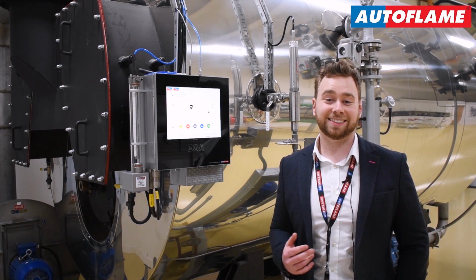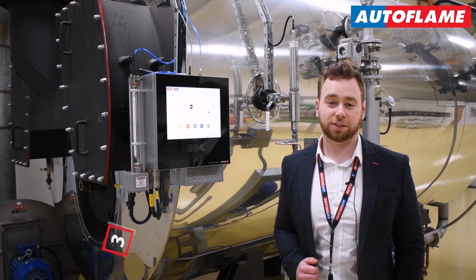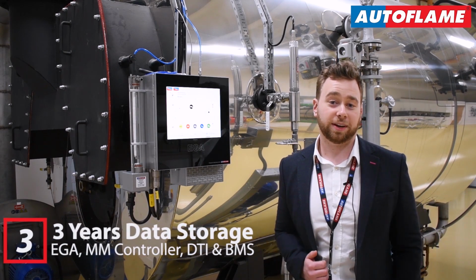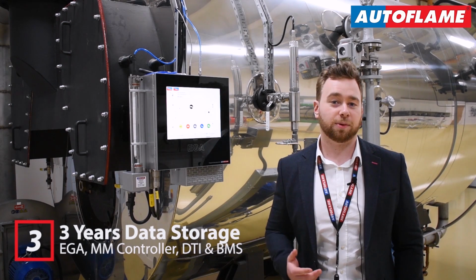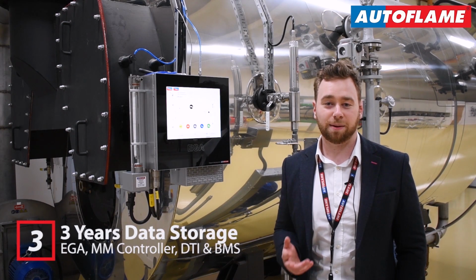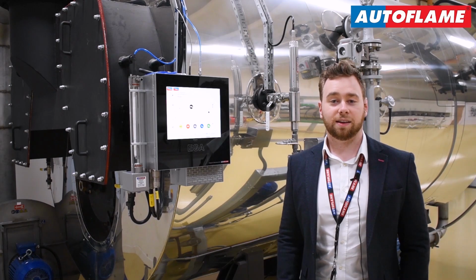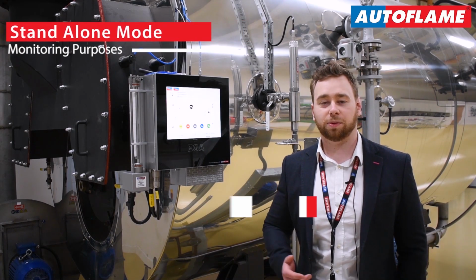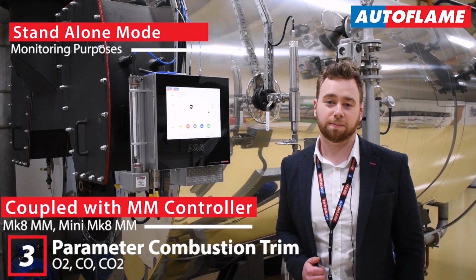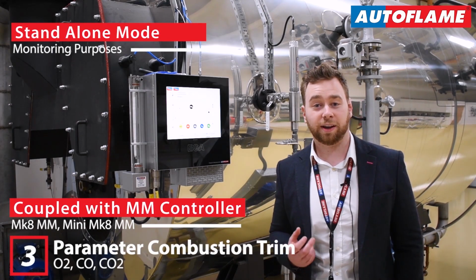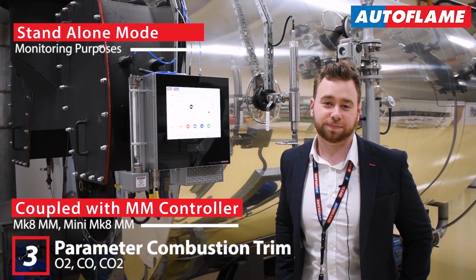This information could be instantaneously viewed through the integrated touchscreen, and this data is then stored for 3 years, and can be accessed through an MM controller, data transfer interface, and a building management system. The EGA can be used in standalone mode for monitoring purposes, or can be coupled with an MM controller for 3-parameter combustion trim. These 3 parameters being O2, CO, and CO2.